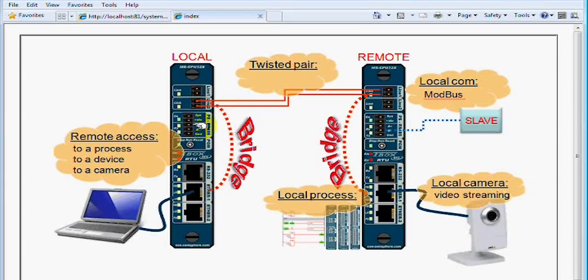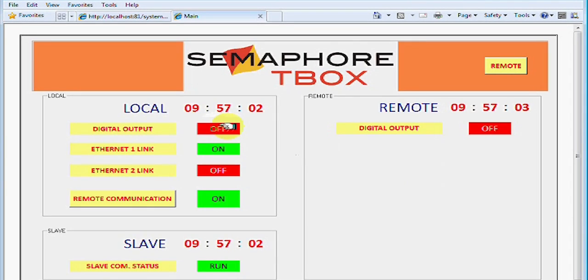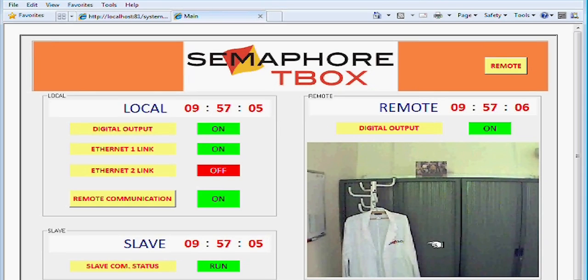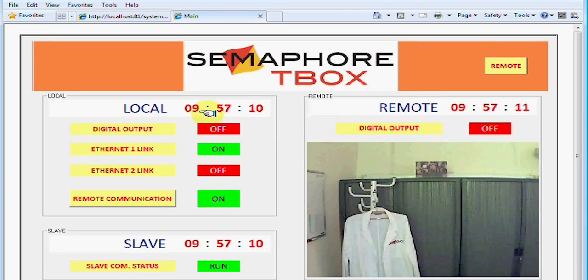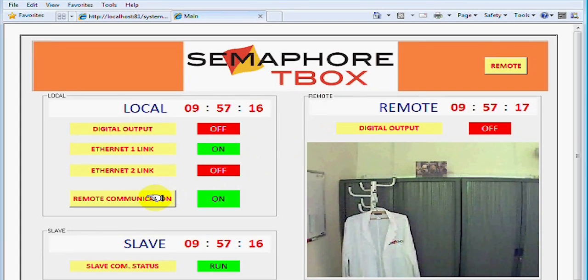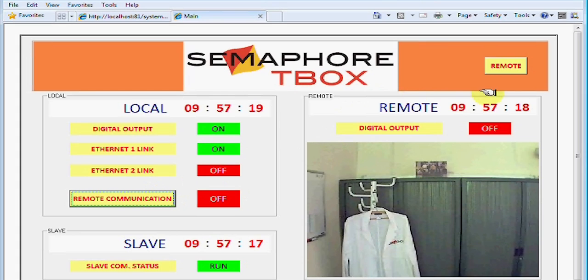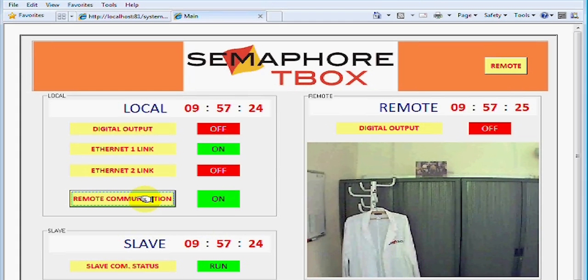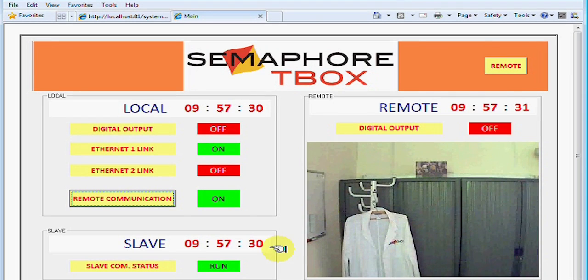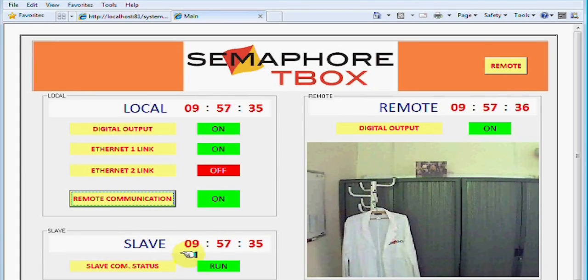Let's go to the local TBOX. One can insert images within the webform. You can see here my office, by the way. Modbus communication is carried out between CPUs — communication that I can stop and start from here. We can see data coming from the remote TBOX is not refreshed anymore. This does not affect at all the display of the image. From the local TBOX, we can also see data and status of the Modbus slave device connected to the remote TBOX.